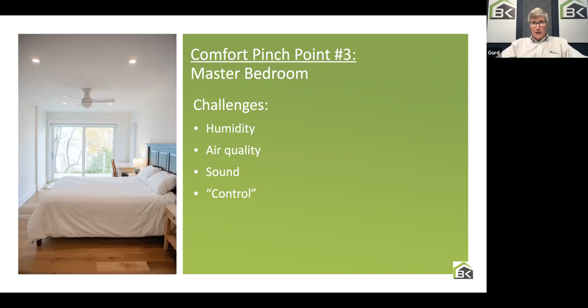So from a comfort perspective, we see this often manifest as cooling issues. They say it's too warm in the space, but when I look at it, it's actually humidity. When I measure and monitor overnight, the humidity is at 65%, and that's impacting comfort. They don't necessarily recognize it as a humidity problem, but the humidity level is rising because of the occupants in that space.